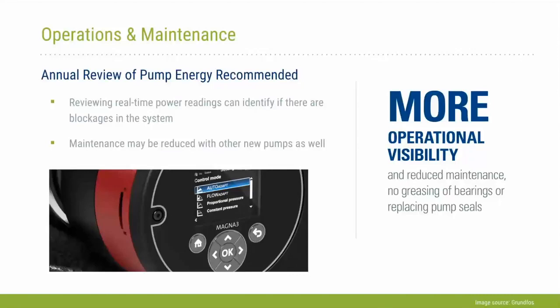So one thing we pointed out is that with the sensors and diagnostics built into the pump, you get real-time feedback from these pumps. Like we said, you can do a yearly review of the power. You can go through and check that power usage to see if you are having any issues with your system, whether it be the domestic hot water or a different circulator application, see how those pumps are responding, and whether anything is lowering your overall system performance. And the other piece we talked about is the reduced maintenance, not having to change those seals and bearings on those pumps.